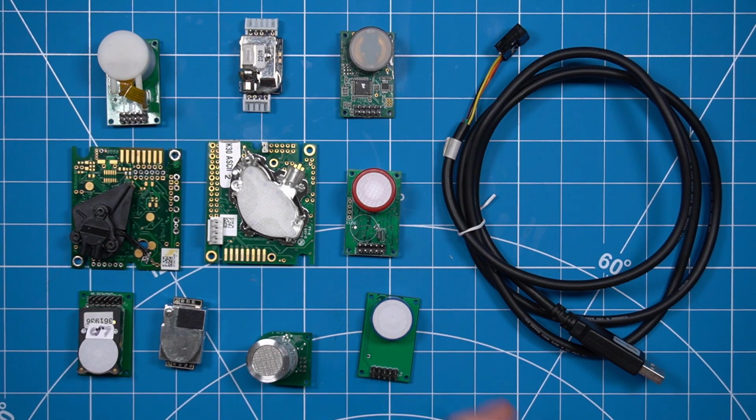You can configure it from zirconia to measure oxygen, to electrochemical for all the exotics, NDIR for the CO2 and a number of other gases, mox oxides, all those kind of things you can talk to. And it's so quick. There are no tools involved and no gyrations and logistics. You simply get to evaluate your sensor right then and there to make sure it's going to fit for the purpose. And I'm going to show you how quickly you can do that.